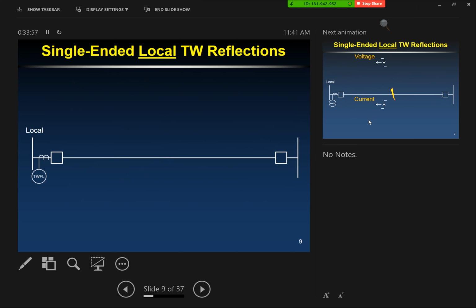On my local end, I have a traveling wave fault locating relay installed, and I wanted to go over the theory covering voltages and currents. From here on, all we care about is currents, because at least the traveling wave fault locating relays I'm dealing with, which are those SEL-411Ls, you have currents and voltages brought in, but your CCVTs and VTs have really bad characteristics for the high frequencies. They don't pass those very well, whereas your CTs do. So we're using CTs to look at this traveling wave phenomenon.